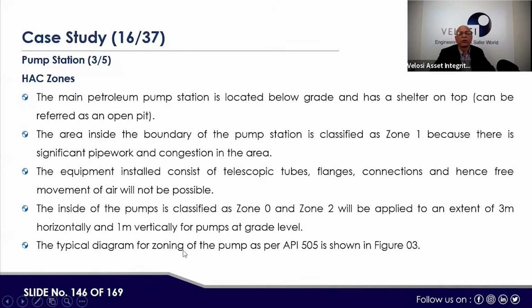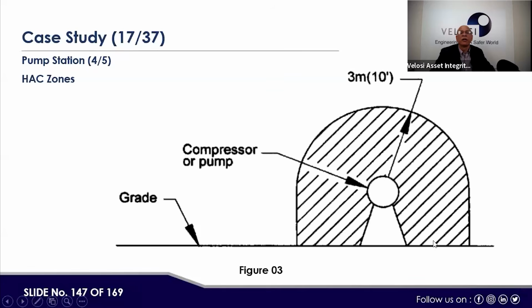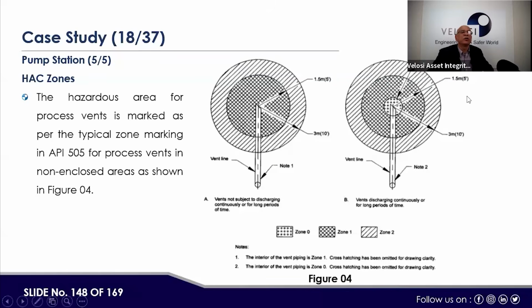The typical diagram for zoning of the pump as per API 505 is shown in figure 03. The figure will be coming. So this is just the pump as we are showing; for a compressor or pump, up to 3 meters outside the pump is basically zone 2. Then HAC zone: the hazardous area for a process vent is marked per the typical zone marking in API 505 for a process vent in non-enclosed areas like this. For the vent, up to 3 meters we take as zone 2, and up to 1.5 meters as zone 1. Zone 0, zone 1, zone 2 is similar to IP-15 or EI-15.